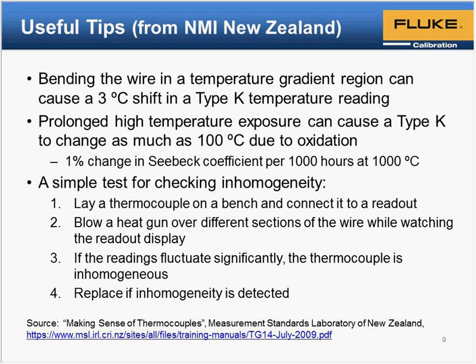It's hard to give you an exact number for inhomogeneity, and that's one of the biggest complications with thermocouple inhomogeneity. It's not really possible to determine exactly what the overall impact of inhomogeneity will be on your measurement, because it depends on what the temperature gradient is, and we'll talk more about why temperature gradient keeps coming up when we're talking about wire inhomogeneity. But the rule of thumb is, if you see wire that is inhomogeneous, it's recommended to just stop using it. If you're getting crazy measurements from a wire, then it's a good idea to do an inhomogeneity test to see if the wire is bad.